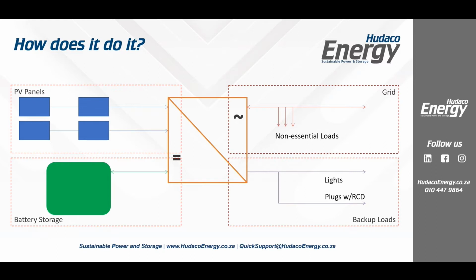and I can run all of these loads, right, off my PV or off my batteries, in fact, if I wanted to, right? Because if we're running in self-consumption mode, I may say I don't want to use Eskom. I would much rather use my batteries for here. Okay, this is a defining different option or a different factor for this solution, which not a lot of other systems in the world have got, and in fact, none that I'm aware of that are doing it en masse from a tier 1 manufacturer locally.